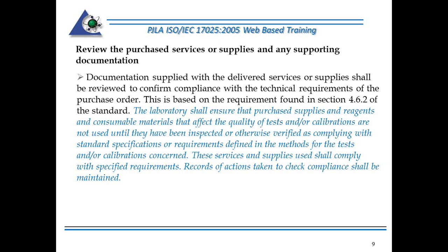So bear in mind that every time you get a calibration certificate, most of you make note of that. Perhaps you note it on the certificate when you received it, and you file it, so it's available for your assessor, it's available for customers, it's available for any parties interested in determining that your equipment is in fact in the current state of calibration. But you do have a responsibility to confirm the calibration certificate, and it's a pretty in-depth determination.